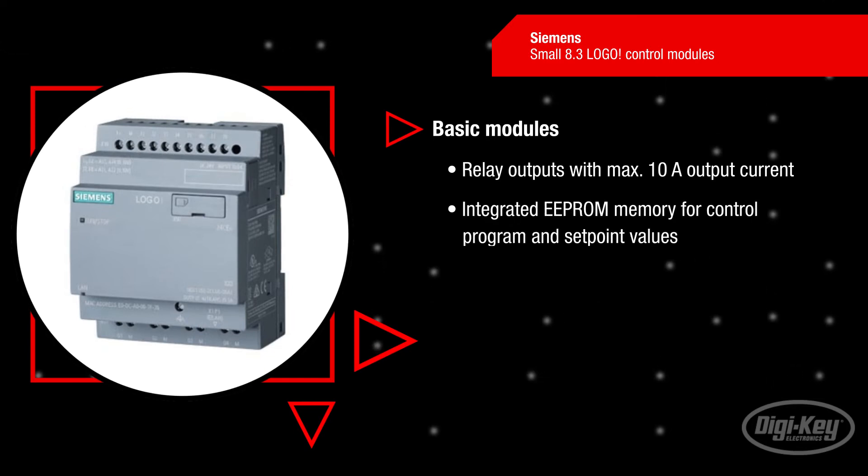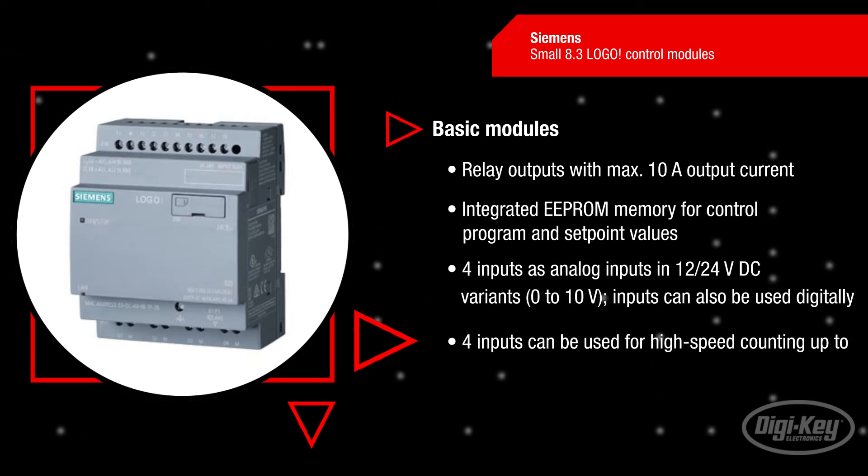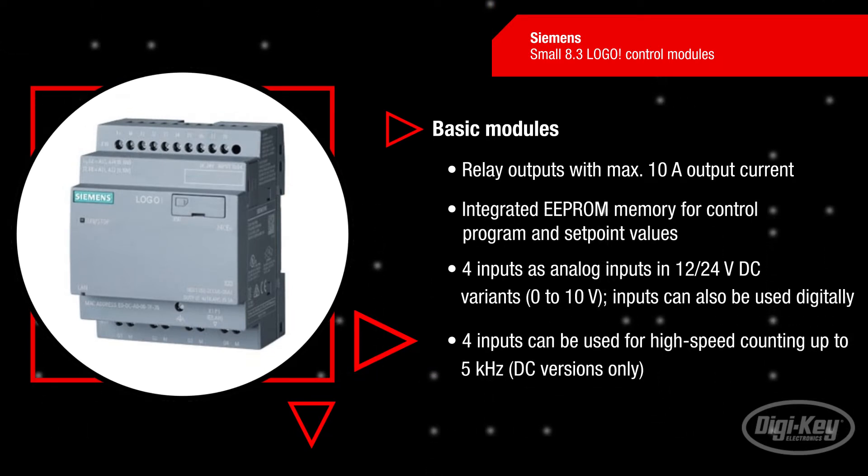The basic modules feature relay outputs with a maximum 10-amp output current. Integrated EEPROM memory supports the control program and setpoint values. The modules offer 8 digital inputs and 4 digital outputs. The 4 inputs can be used as 12 or 24 volts DC analog inputs in the DC variants, with an input voltage range from 0 to 10 volts. The inputs can also be used digitally, and in the DC versions, the 4 inputs can be used for high-speed counting up to 5 kilohertz.